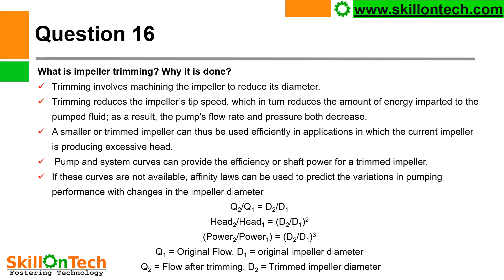As per affinity law: Q2/Q1 = D2/D1; H2/H1 = (D2/D1)²; P2/P1 = (D2/D1)³. Where Q1 = original flow, D1 = original impeller diameter, Q2 = flow after trimming, D2 = trimmed impeller diameter.